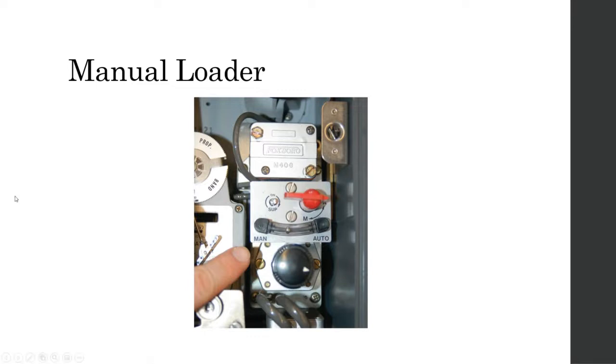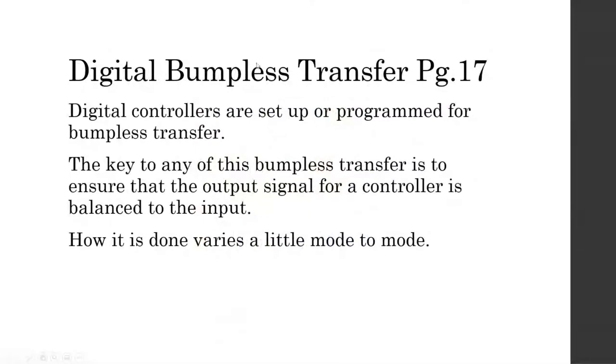So it can be done the old school way, it can be done the new school way. The new school way is obviously probably much easier. So digitally, or the new school way, we set them up or program for bumpless transfer. And again, regardless of whether it's pneumatic or digital, the key to any of this bumpless transfer stuff is to ensure that the output signal for a controller is balanced to the input signal from the other controller.